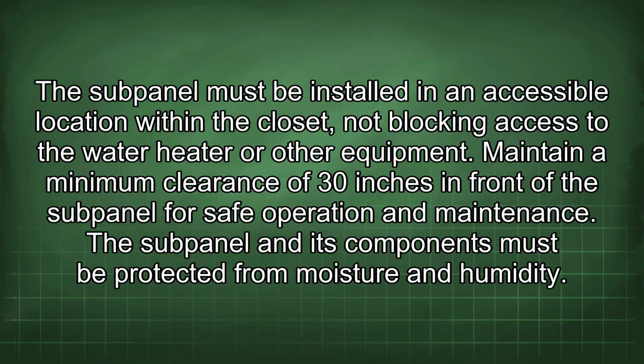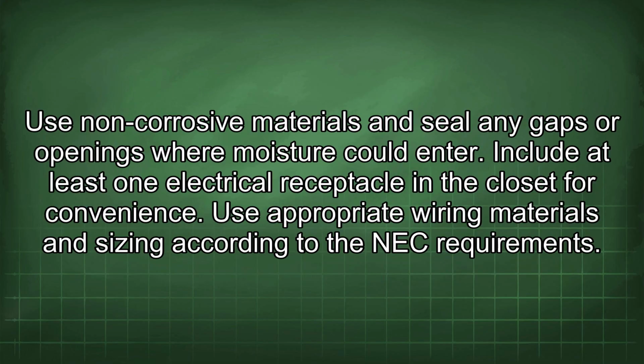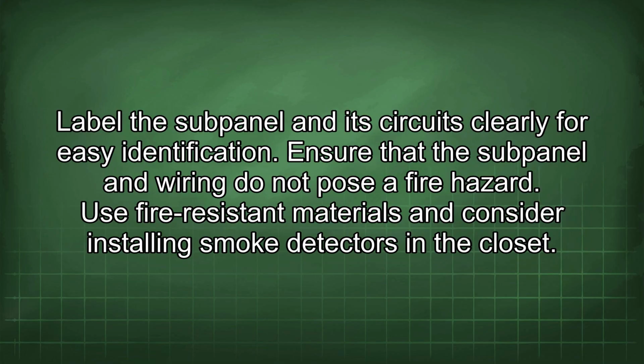The subpanel and its components must be protected from moisture and humidity. Use non-corrosive materials and seal any gaps or openings where moisture could enter. Include at least one electrical receptacle in the closet for convenience. Use appropriate wiring materials and sizing according to the NEC requirements. Label the subpanel and its circuits clearly for easy identification.